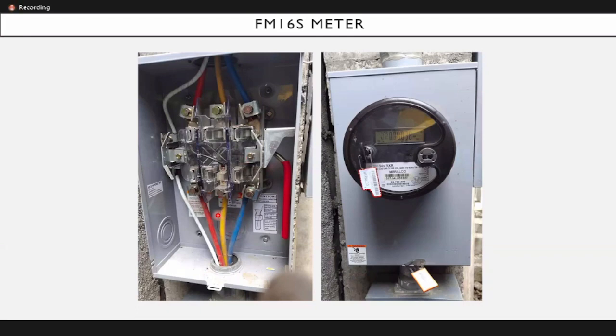Normally, the standard is phase A is at the leftmost, or this one, the color red. Phase B is at the center, or the yellow one. Phase C is the blue. And a white one is the neutral or ground. This is the lever. It functions so that during meter replacement, pwede po namin gawing mag-replace ng meter na hindi madi-disrupt or ma-interrupt ang power ni consumer.